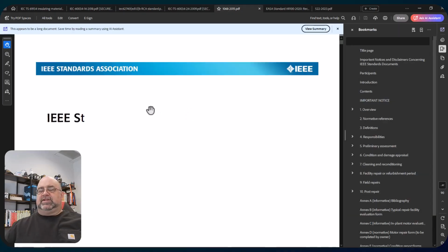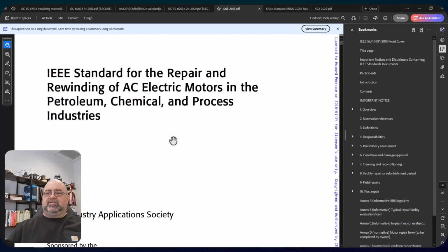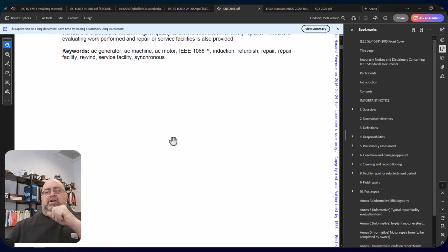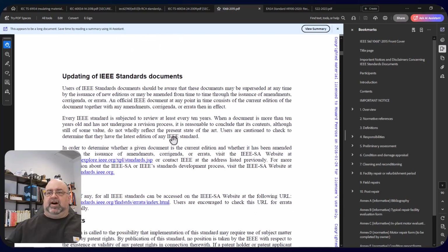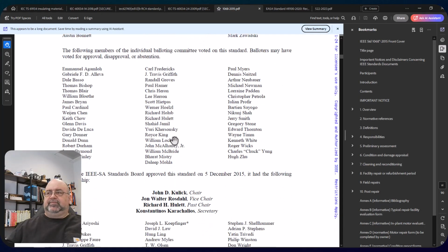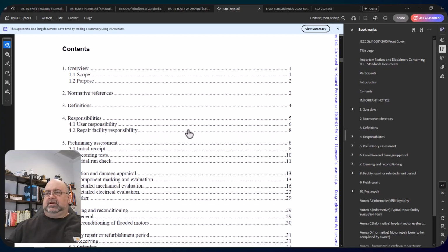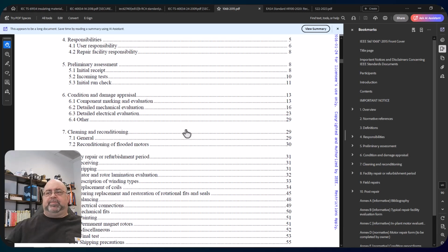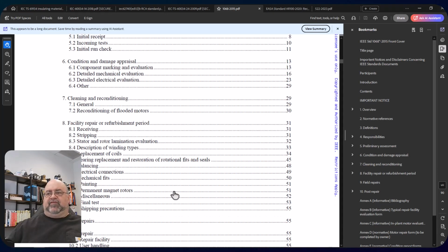1068, here we go. So this is a standard for the repair and rewinding of AC motors, and it does include sections related to surge testing of insulation systems. I wasn't on this version, and that was a problem. I was kind of kept off of it. And it now allows for a 20% increase in core loss per repair, which I find interesting, seeing as I keep being told in public that I'm wrong, that there is no increase in core losses through the repair process. But the same organization that's been making that statement is the same organization that insisted that 20% be included in here. Go figure.